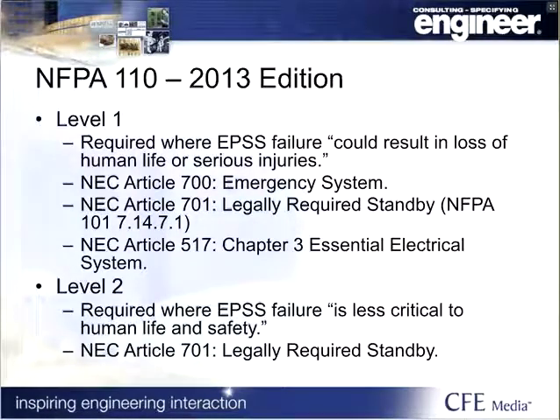A Level 2 system is required when failure is less critical to human life and safety. Depending on other applicable codes, NEC Article 701 systems would generally fall under this level. A good way to look at this is that systems used to safely evacuate occupants from the building would be Level 1. Other systems where loss would negatively affect rescue or firefighting would be considered Level 2.